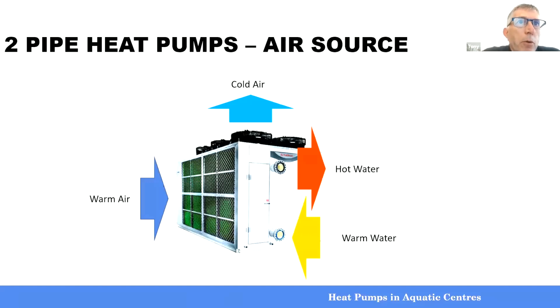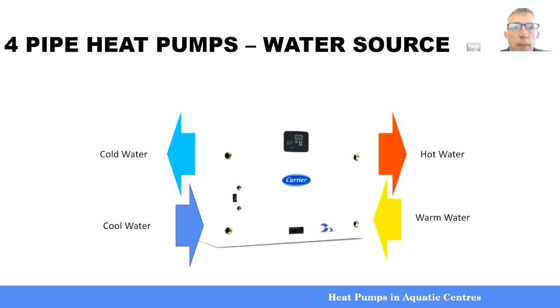Even though I assume you're all aware of the basic operation of heat pumps, I'll start simple. A two-pipe heat pump has two pipes: warm water in and warmer water out. When heating, all heat pumps also need to cool something. A two-pipe heat pump cools the air, so it uses air as its heat source. Four-pipe heat pumps have four pipes; as well as heating water, they are also cooling water at the same time. It uses water as the heat source, and this kind of heat pump is used when there's an alternative source of heat other than air available.